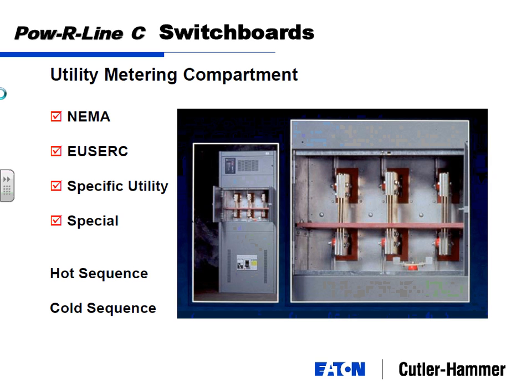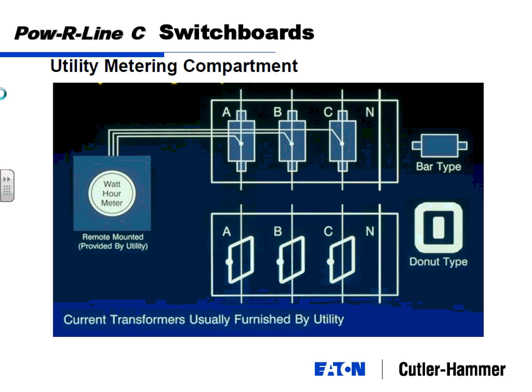So if you did want a utility meter compartment, this is about what it looked like. This compartment here is blown up, and basically it just looks like copper links in between all those phases. So Xcel, for example, would send out CTs to the contractor. He'd pull out these 3 copper links and put CTs in there. Each CT would have a lead that would then run to a utility wire, looking just like this up here at the top. Bar type CTs. You'd run the wires to a watt-hour meter that you maybe mount on the side of the building or what have you.